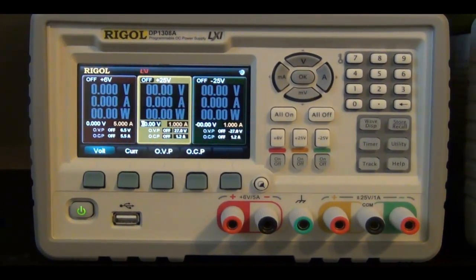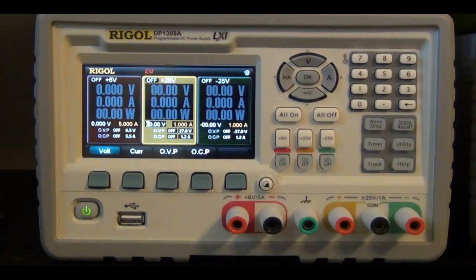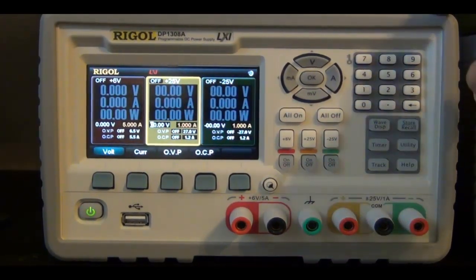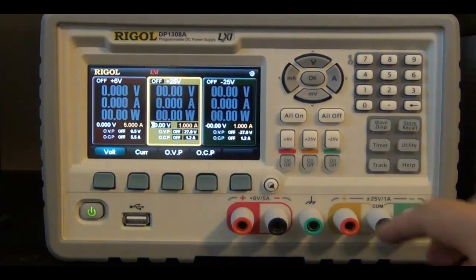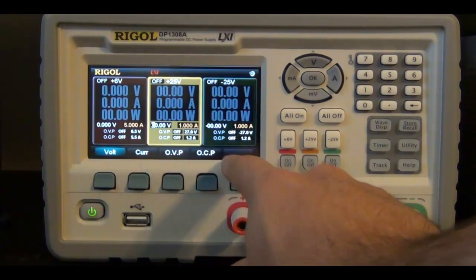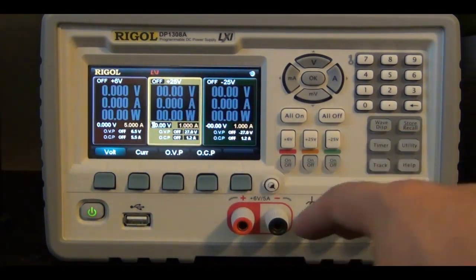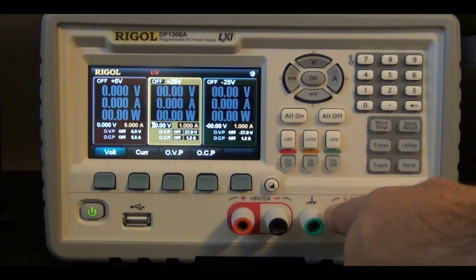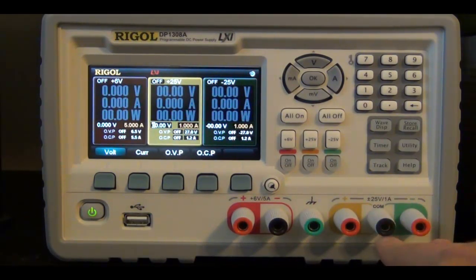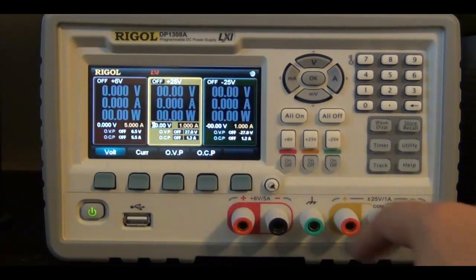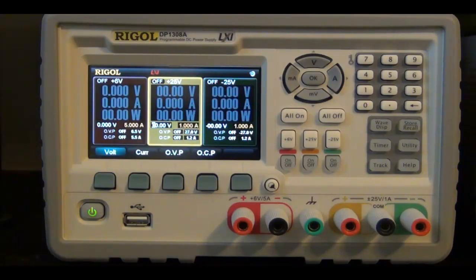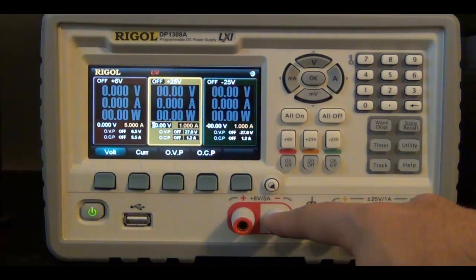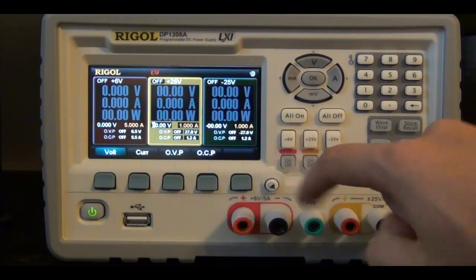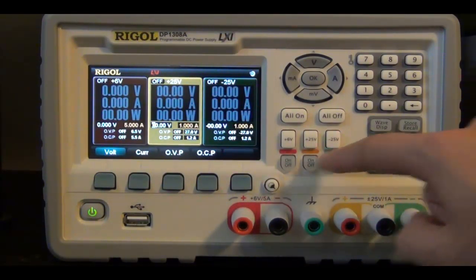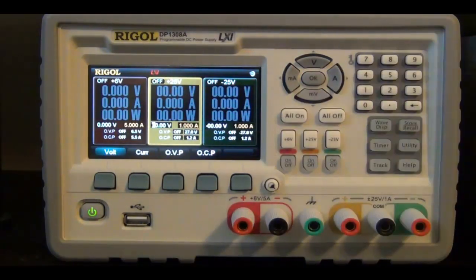There we go. So the layout is of course the same, with the difference that because this one has triple output, as soon as you turn it on, you get three individual cards that tell you the setting for the 6 volt, the plus 25 volt, and the minus 25 volt output. By default, all the outputs are of course turned off, and they're all set to 0 volts. Now, if you want to select a particular channel, all you need to do is press the button for it. They're color-coded here, and the color-coding matches the color on the LCD.